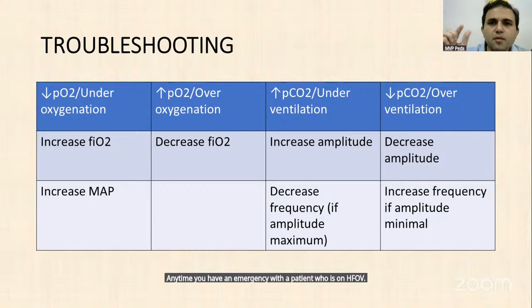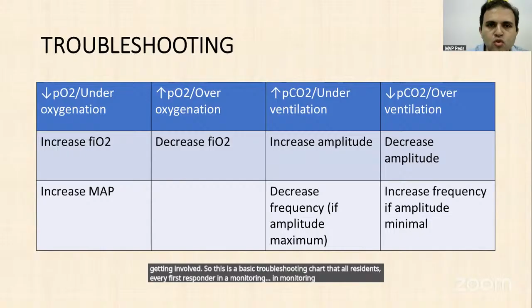So the basics of troubleshooting are, if your PaO2 is low, that is the patient is under oxygenated, increase the FiO2 in the short term, but increase your mean airway pressure. So increase MAP. If you are over oxygenating, of course, you reduce the FiO2. If your CO2 is high, that means you are under ventilating this patient, increase the amplitude or delta P. And if your CO2 is low, that is you are over ventilating, that means there is CO2 washout, please decrease the amplitude. Although I've written frequency, these are not things that we will touch usually in high frequency much without consultants getting involved. So this is a basic troubleshooting chart that all residents, every first responder in monitoring an HFOV patient should know.